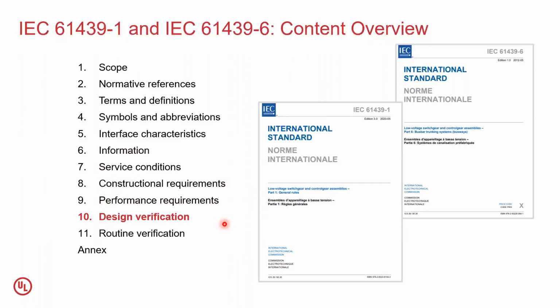Clauses 8 and 9 are essentially ways and means to prove that your product complies with this standard. Clause 8 talks about the construction requirements, and clause 9 talks about the performance requirements. To meet both construction and performance, there is a certain amount of verification that one has to do, and this is brought under clause 10, which is the design verification. That's why I have highlighted it here, because if you understand the design verification, you will probably have understood most of the compliance requirements in those standards.